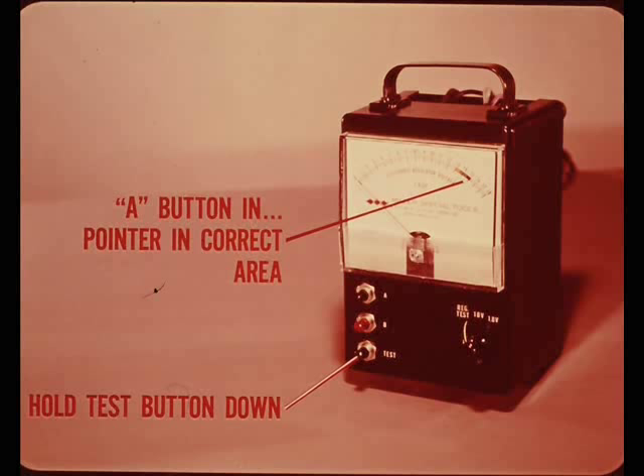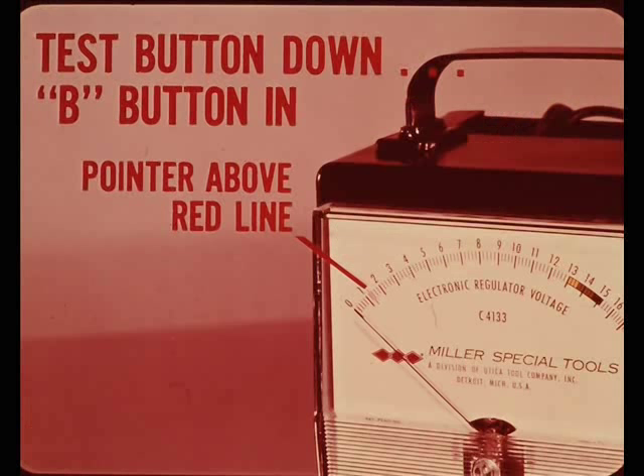Then release the A button so you can make the final regulator test. Keep the test button down and push in the red B button. The pointer should now read above the red line on the dial. When you finish testing, remove the test connector and power cord plugs, but leave the ground clip in place so you can use the tester as a voltmeter.